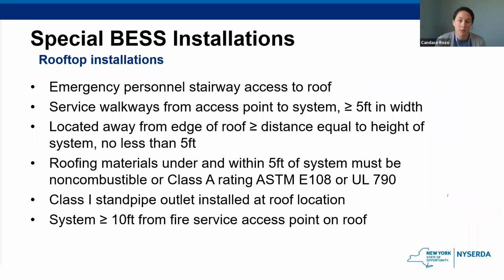So here we have the specific requirements for the rooftop installations. You have to make sure of emergency personnel stairway access to the roof, and that service walkways from the access point to the system are at least 5 feet in width and located away from the edge of the roof, and that roofing materials under and within 5 feet of the system are non-combustible. This is also where they have a requirement for the class 1 standpipe outlet installed at the roof location. That dry standpipe that we had discussed earlier in the presentation, this is where it is required. And then the system should be at least 10 feet from the fire service access point on the roof. Once again, that makes sense, because you don't want your firefighters getting to their normal roof access point and having the system within 10 feet if there's an issue. So you just want to make sure that all of these requirements are on the site plan that the developer is providing you.